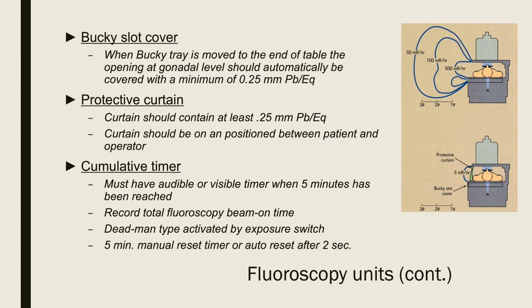When you're looking at a cumulative timer, we have a 5-minute timer, and that's going to record the time the beam is on, or fluoroscopy time, when you're fluoroing. And then it has a 5-minute manual reset. And that is it.